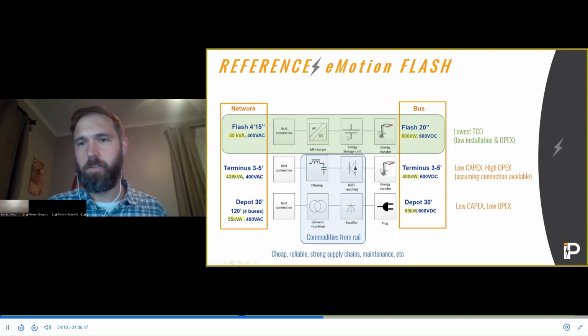Since they only need a stabilized voltage from the infrastructure, they can use a battery in the infrastructure as the charger. A small 50 kilowatt charger constantly recharges this storage battery, and when the vehicle arrives it does a 600 kilowatt battery-to-battery fast charge. So the grid infrastructure never sees the full 600 kilowatts, only about 55 kVA, or roughly 50 kilowatts.